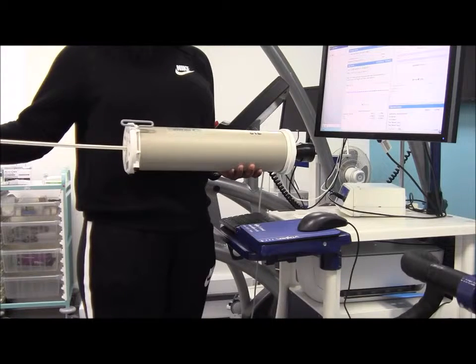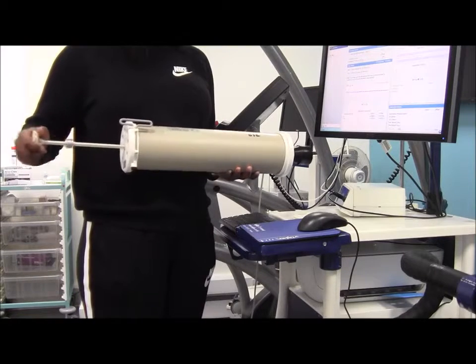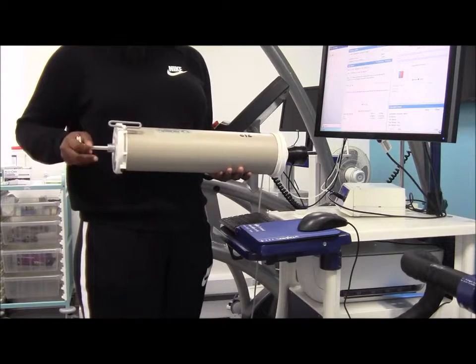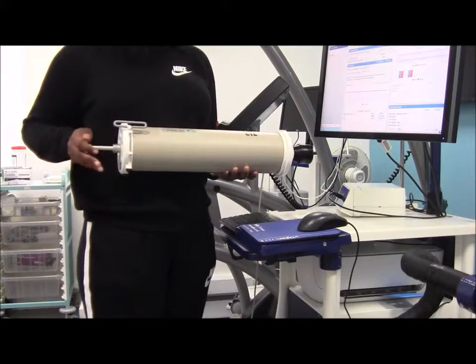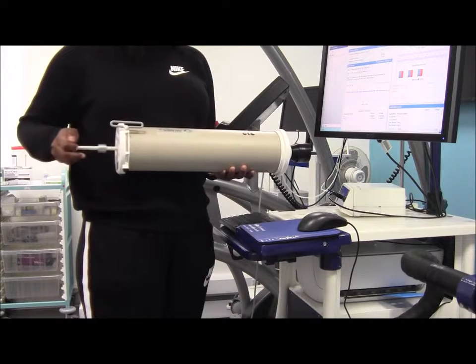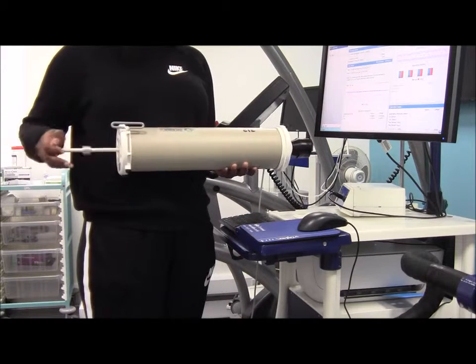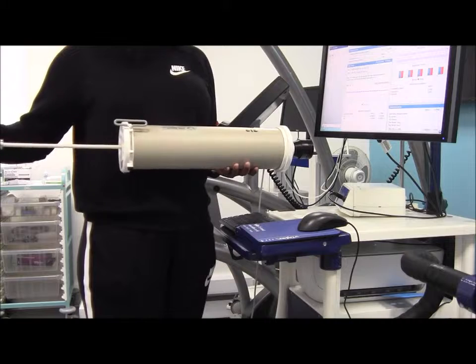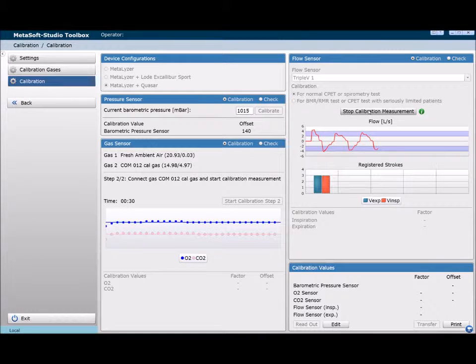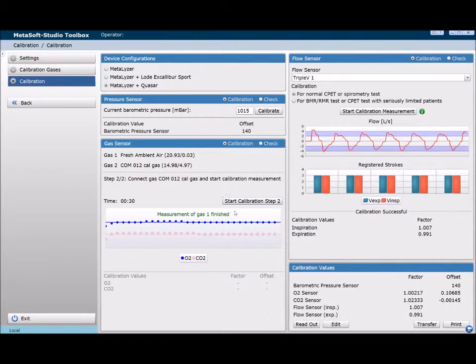The aim of this is to get the minimum and maximum flow values between the two shaded blue range of the calibration measurement graph. Use the 2 rhythm bars at the bottom as guidance for performing suitable pump strokes. Once 5 valid strokes have been registered, click Transfer to complete the process. If more details about the calibration is required, then click the Readout button.